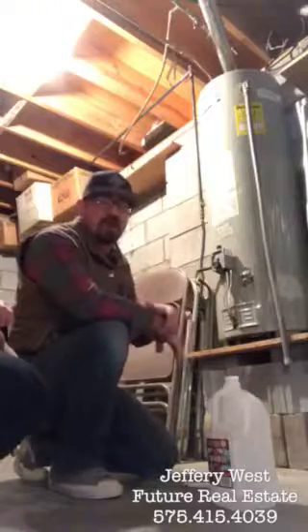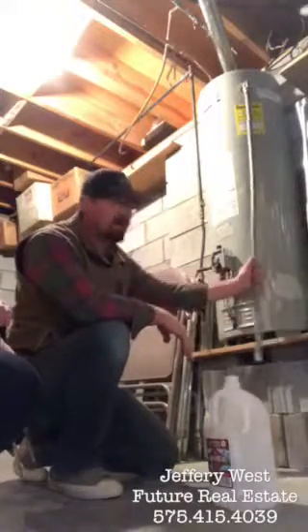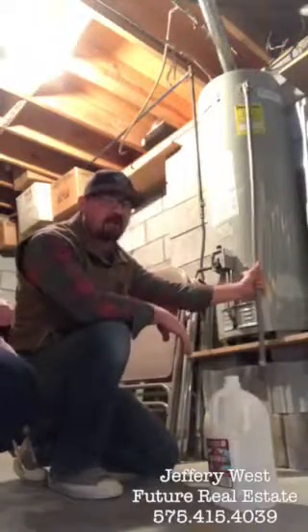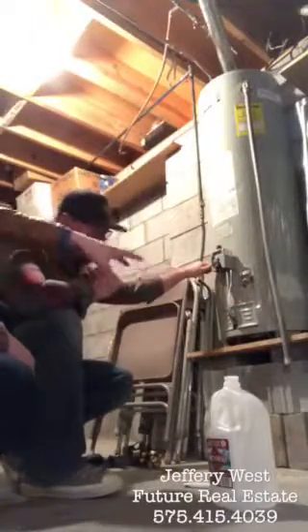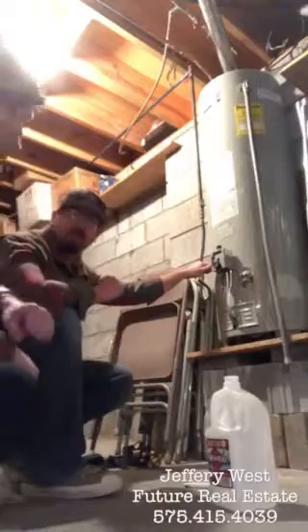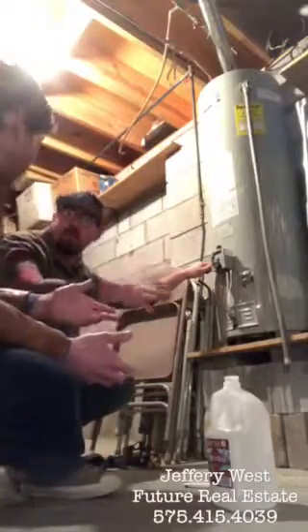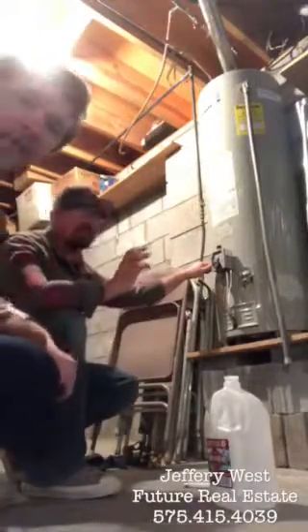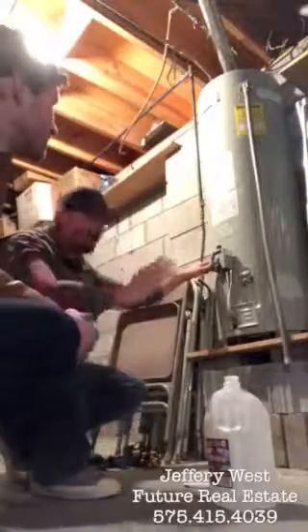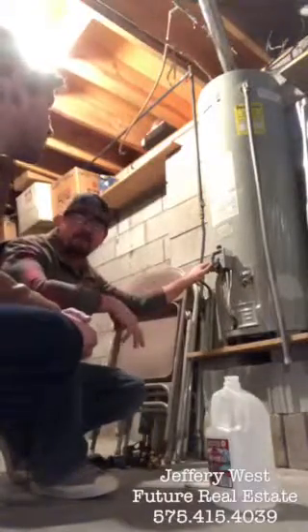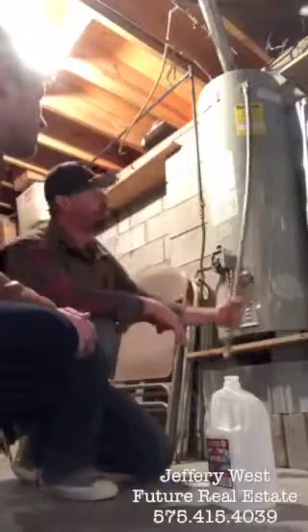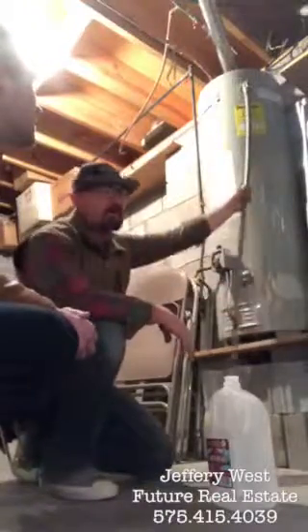If it ever gets too much pressure, it just discharges out of this line right here. So the hot water comes out of that line, and if you don't have that line, and it discharges while you're standing near it, or next to walls or personal belongings, it can create a lot of damage to the area. So we always want to make sure our TPRV valve is hooked up correctly.